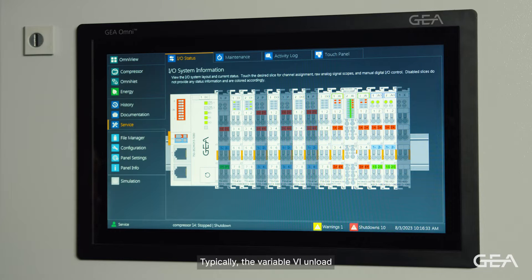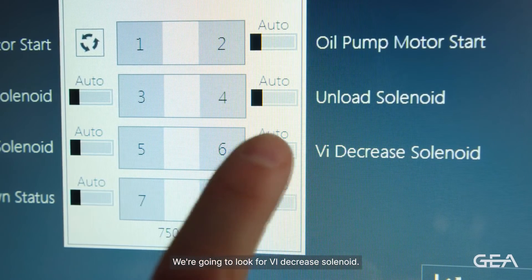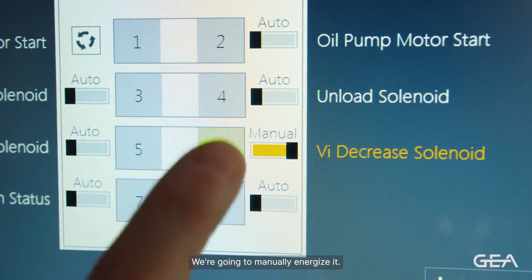Typically the variable VI unload is going to be on one DO, or one digital output slice. We're going to tap on that slice and look for the VI decrease solenoid, then manually energize it.